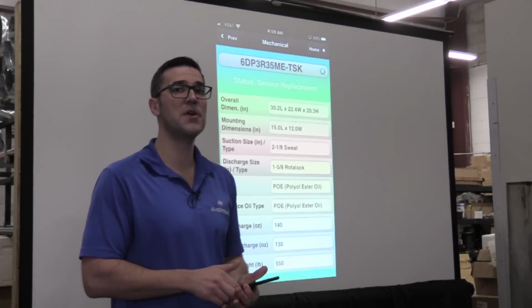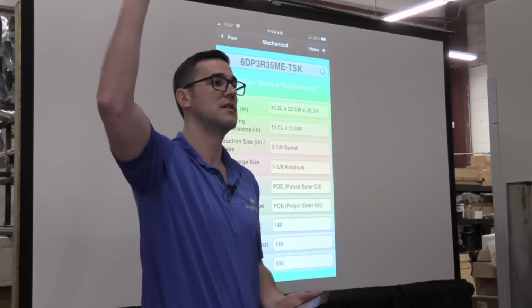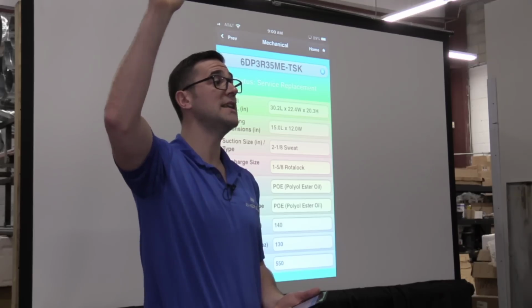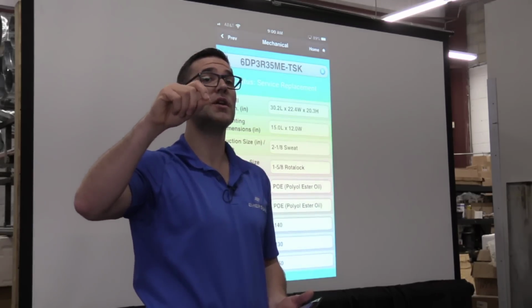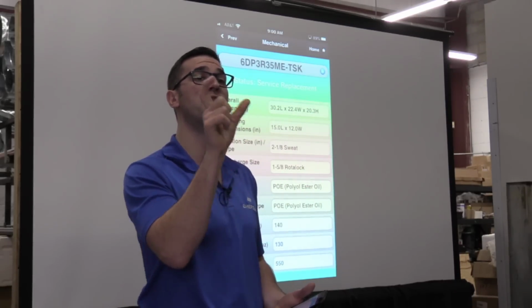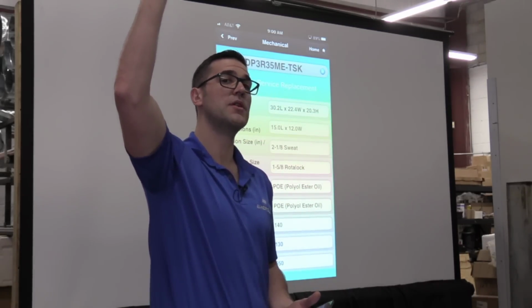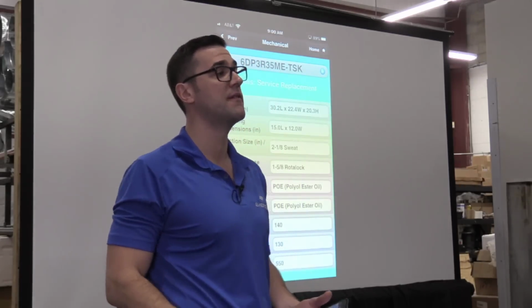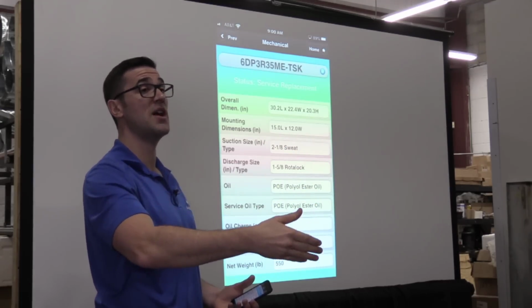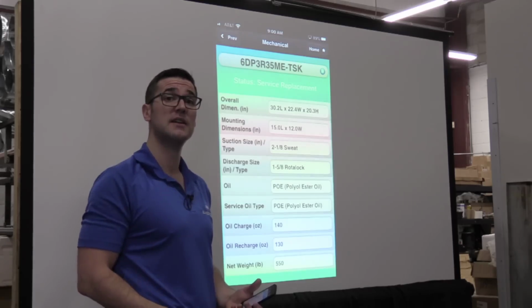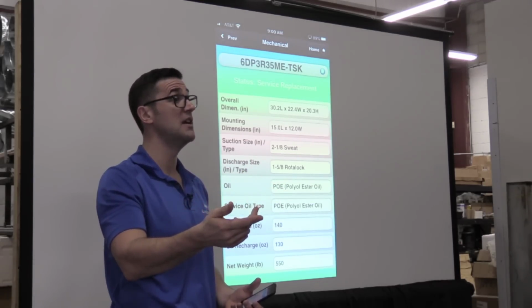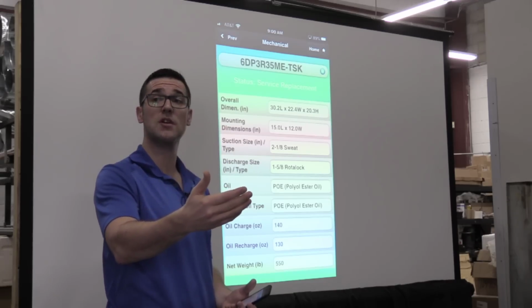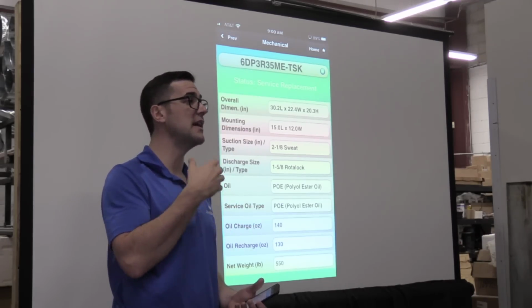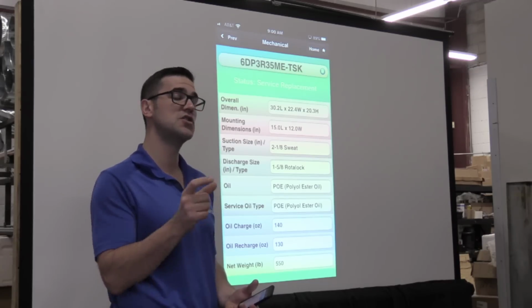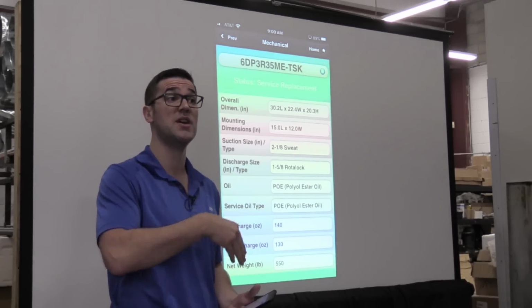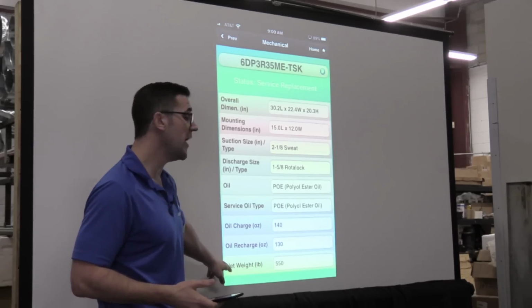So how many people know much about bill of materials on compressors? Show of hands. Not many, right? How many people write the full model number out when they're going to go into a Copeland authorized wholesale and have that full model number? Show of hands. Better start putting your hands up because those last 3 numbers mean a lot of stuff. So I can tell if that's a new compressor, if it's a service compressor. I can tell, depending on the model of compressor, what parts are in that. Does it have electrics? What type of feet? Are they hard feet, soft feet? Very important to have that bill of materials for your distributors, because the guys that are promoting and stocking our product need those 3 numbers. So make sure you write the bill of materials down, because that's going to help you get the right parts for that compressor.